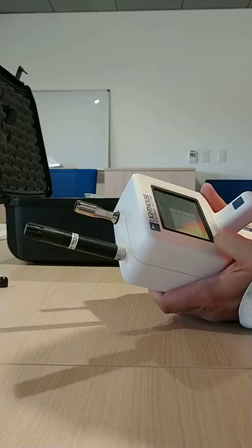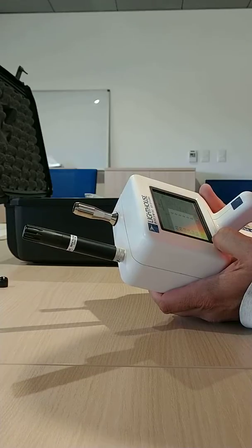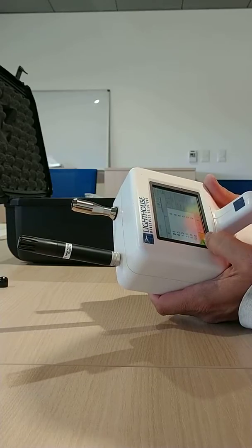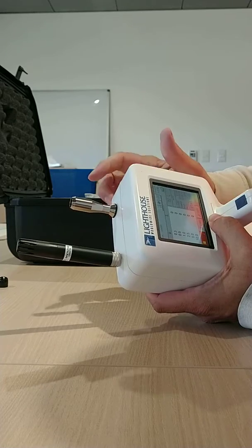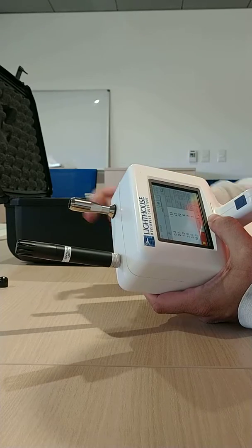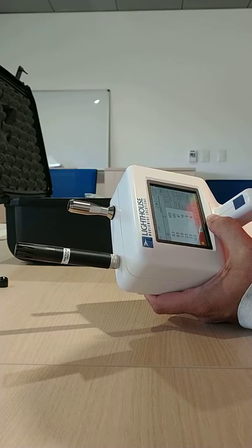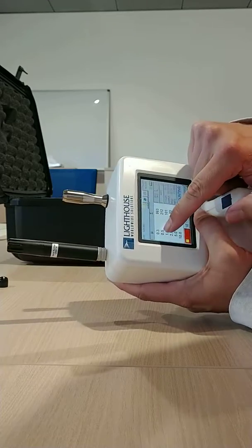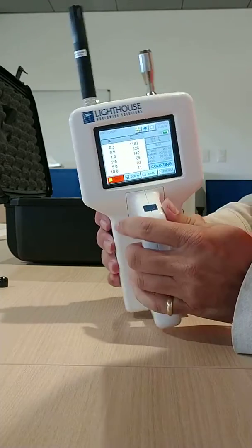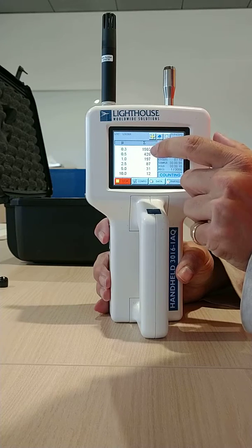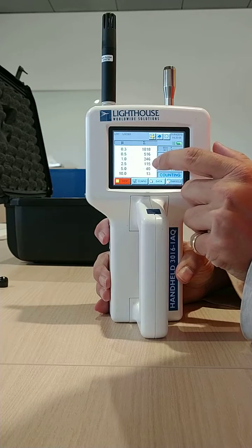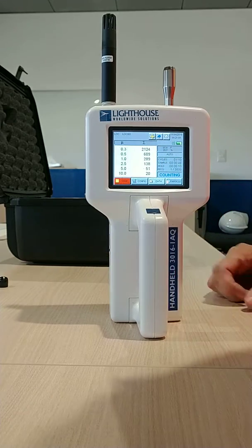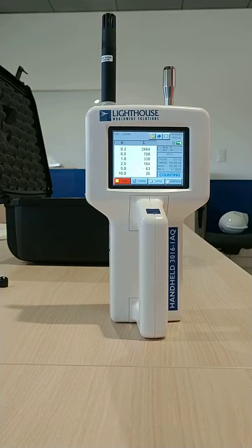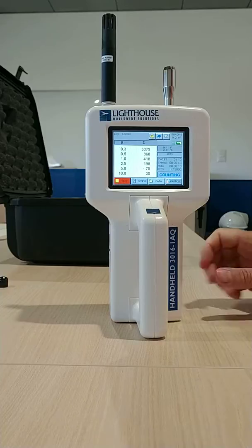It's set up to do 1 minute samples. So if you hit start, you'll hear the vacuum working. The air is being sucked in through this hole, and it's counting particles of 0.3, 0.5, 1 micron, 2.5 microns, 5 microns, and 10 microns. And you can see that here in the conference room on the summit, the number of particles is large.